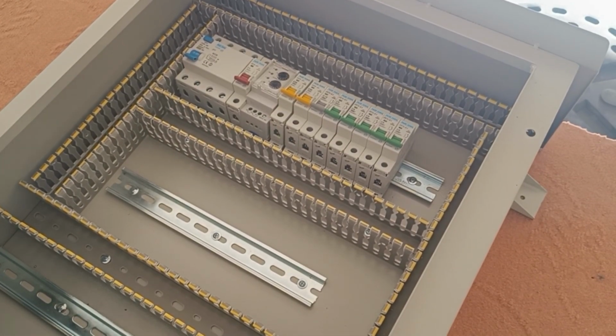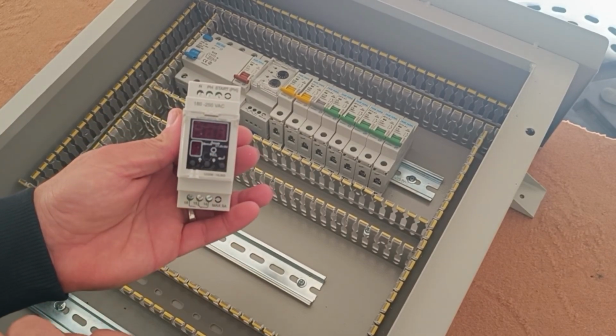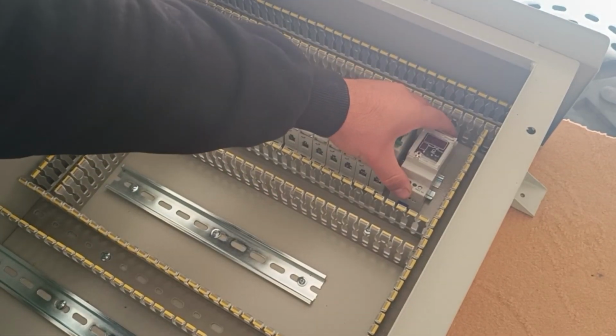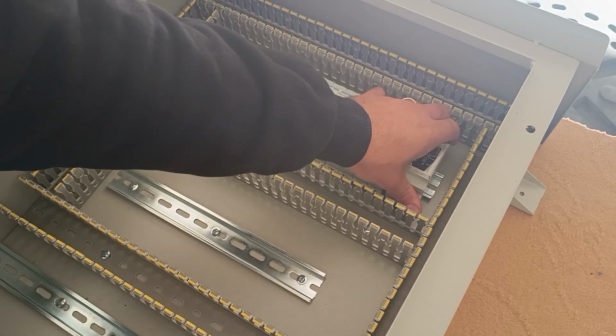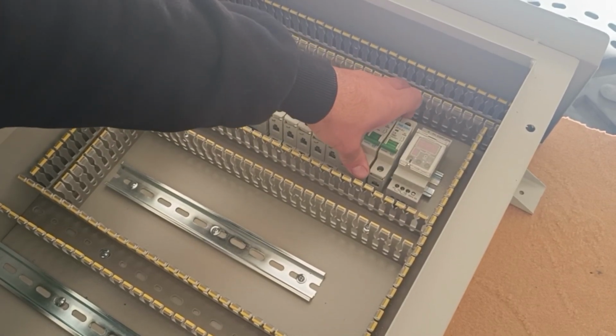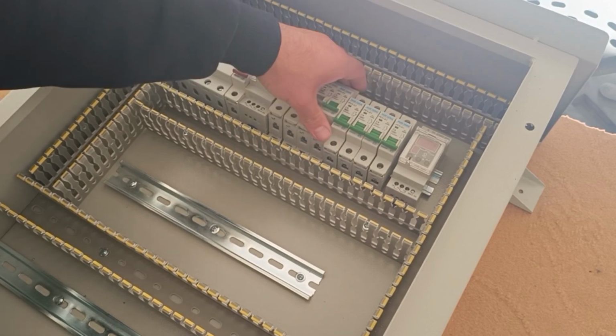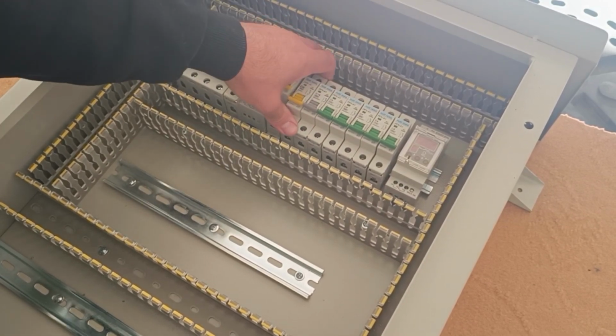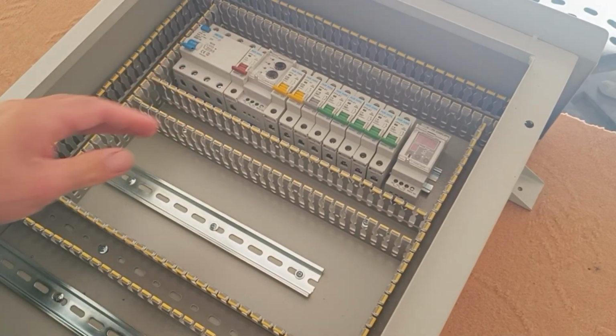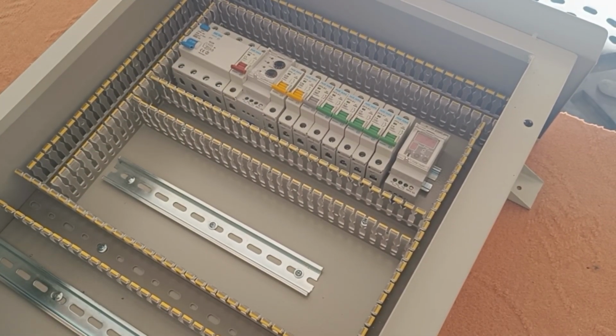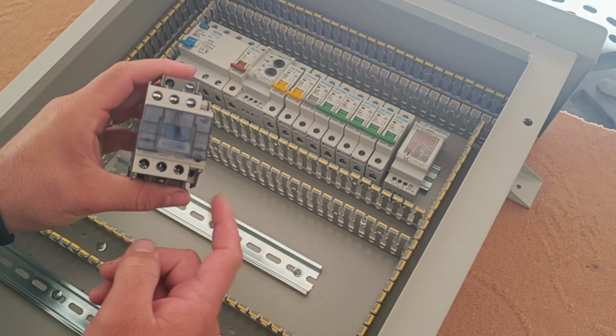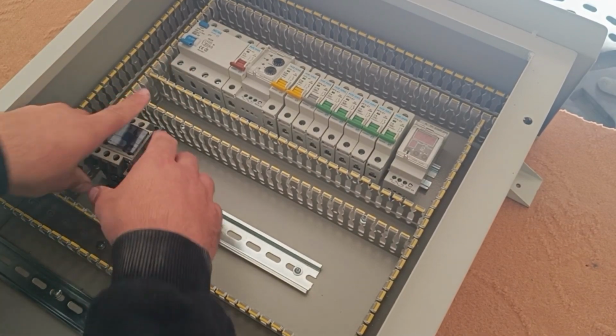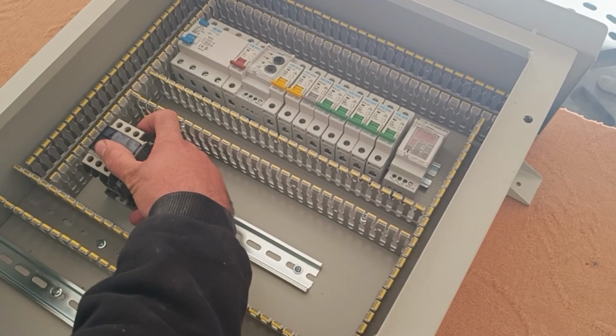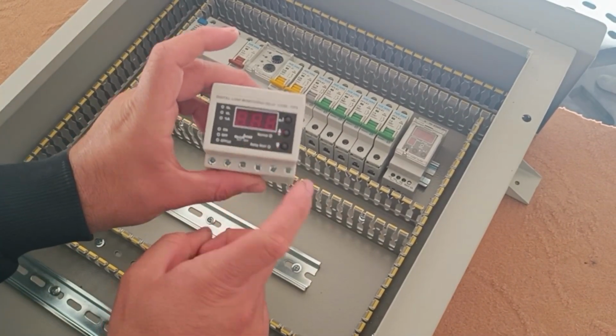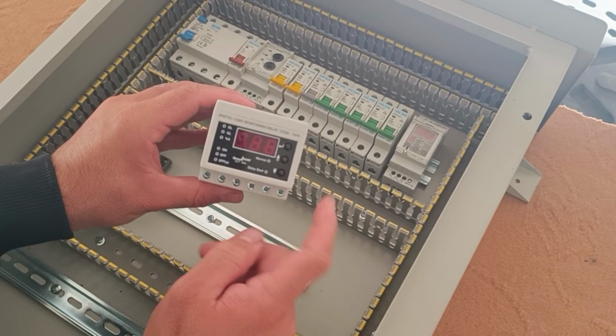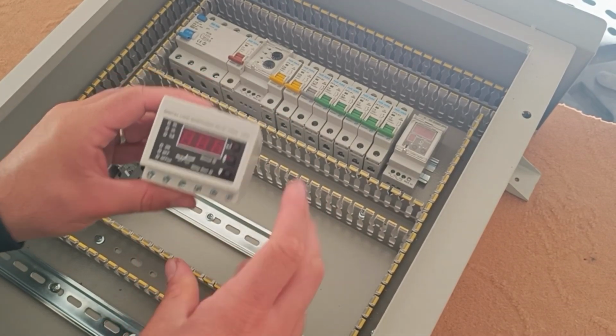This electrical panel includes a three-phase contactor output that operates on a timer. This is a timer relay for it. This is a contactor for the three-phase output. To protect the three-phase output from overcurrent, we also use a current monitoring relay, which is installed alongside the contactor.